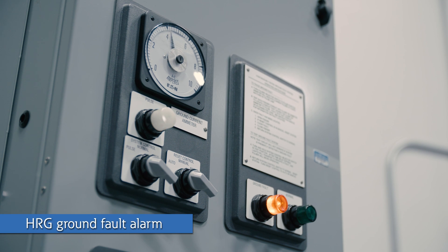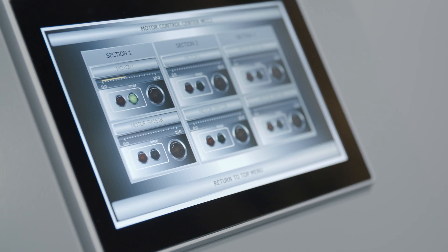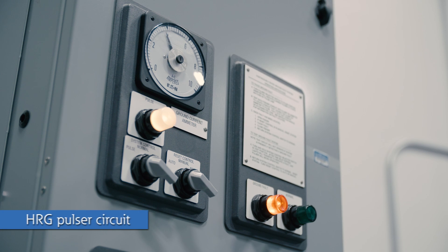When a ground fault occurs, the HRG sets an alarm that alerts building personnel. It is signaled by a light on the HRG, and the HRG can also send a ground fault indication to a monitoring system to alert remote personnel. The HRG also has a built-in fault tracing means through the pulser circuit.